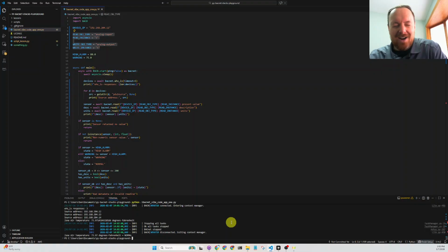You can, I think, if you do some really complicated BACnet broadcast management device, a BBMD, but I never get into that, and people don't do that in the wild. Contractors set up unique BACnet devices in a real HVAC system. Each component on the HVAC system is its own BACnet device. And I think it's best to just mimic that, how people set it up in the field.